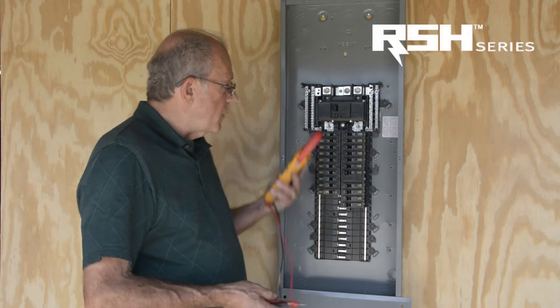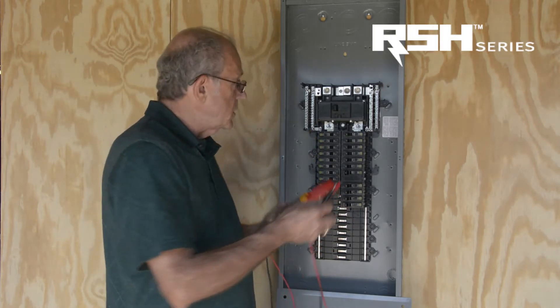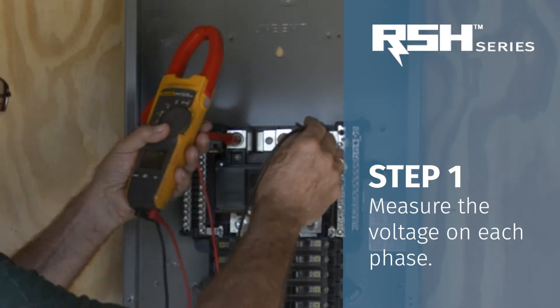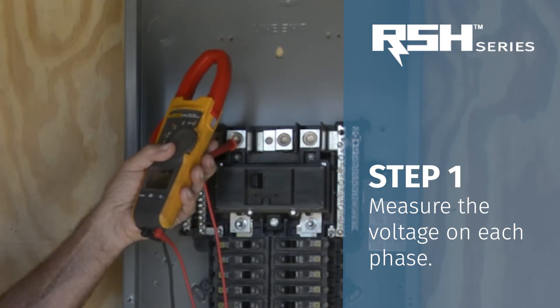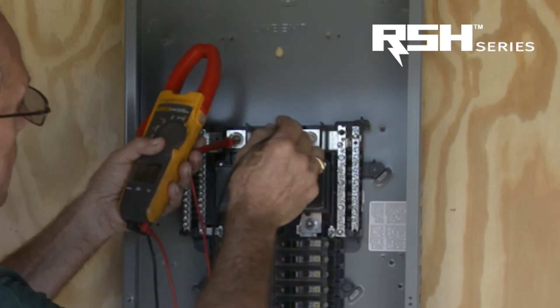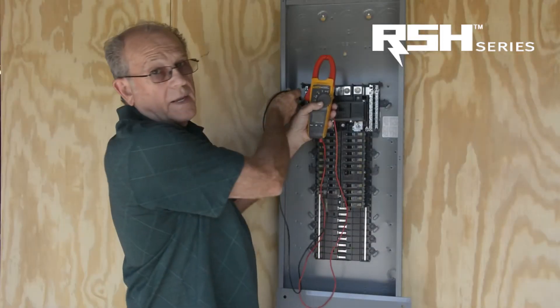We have now removed the cover of the panel. The first thing we are going to do is measure the voltage and make sure that we have the appropriate voltage. We have 240 line to line, and we have 120 line to ground and 120 line to neutral.